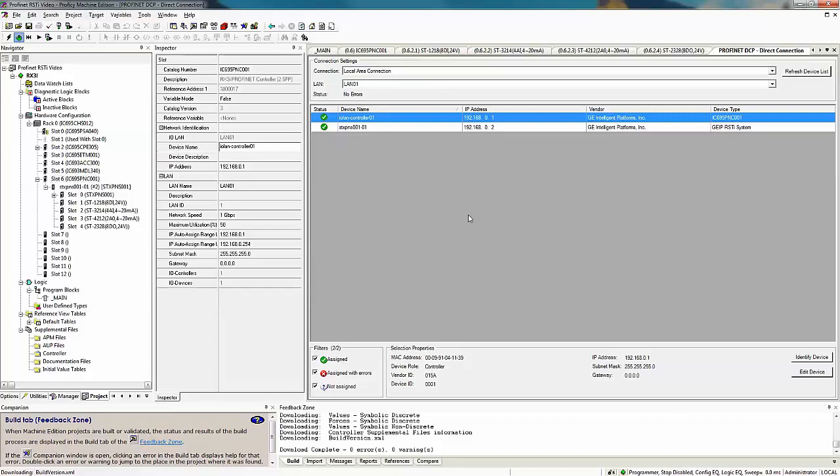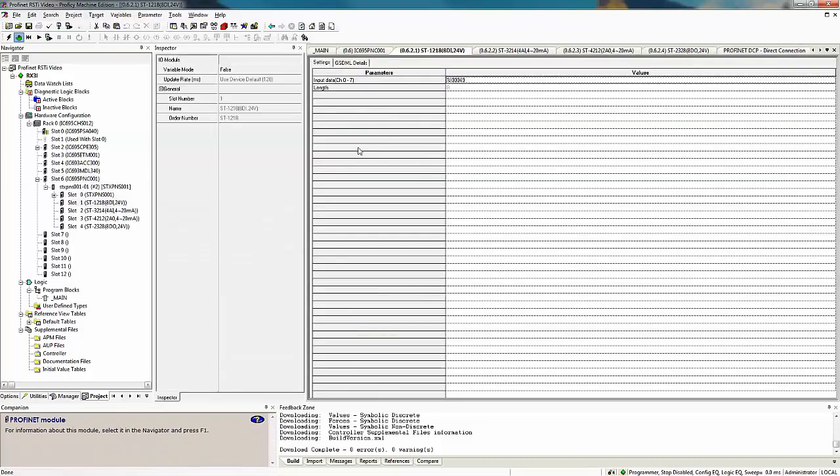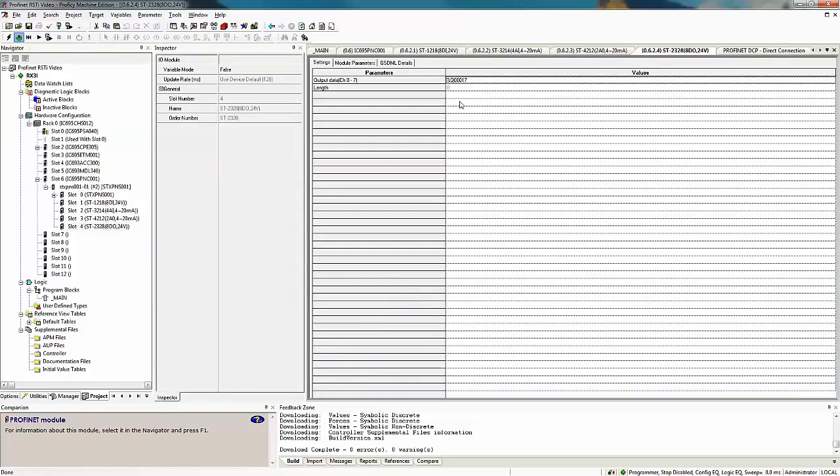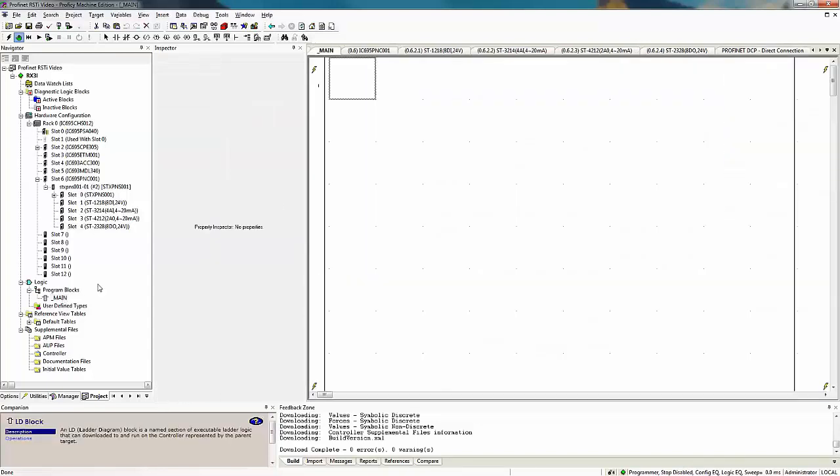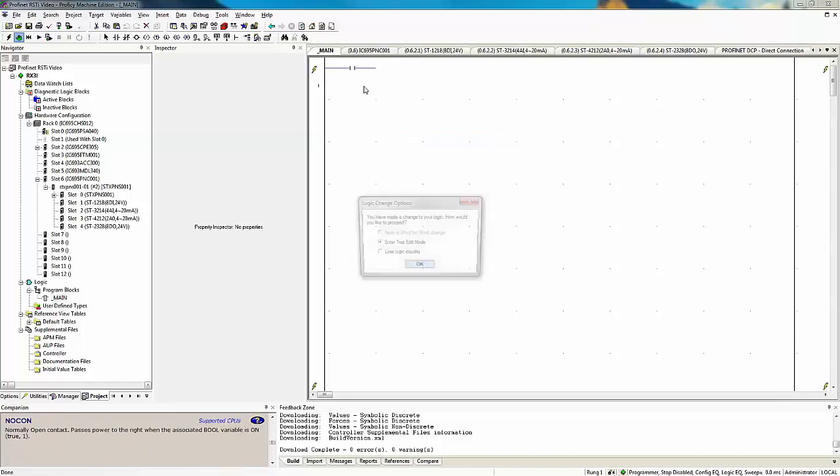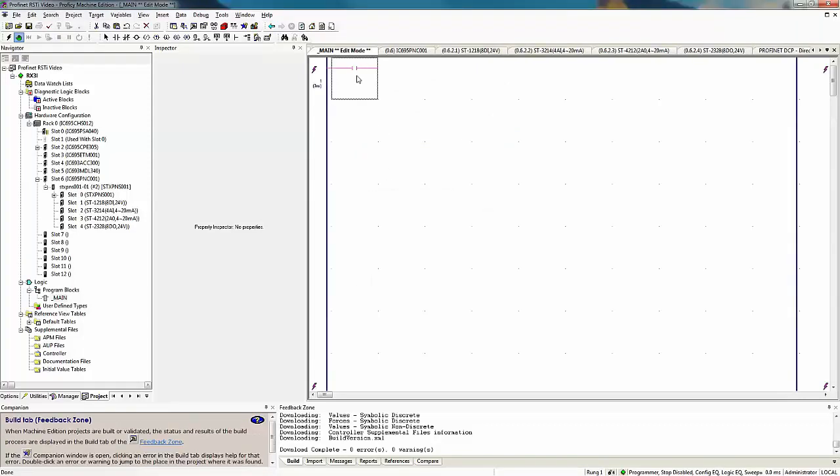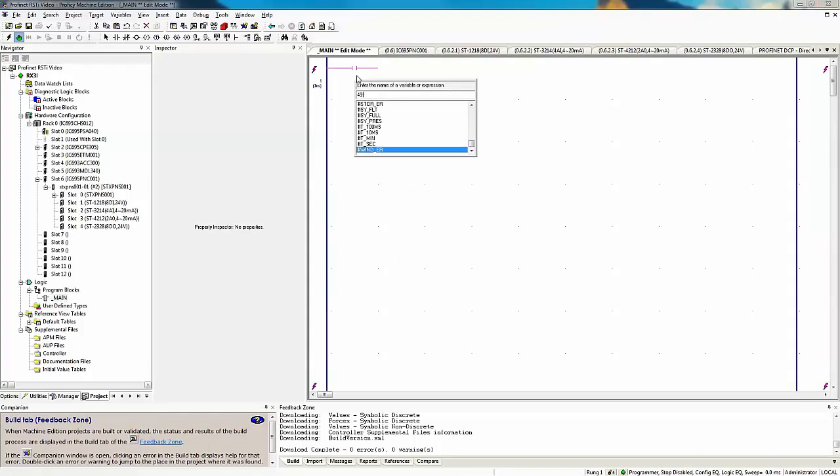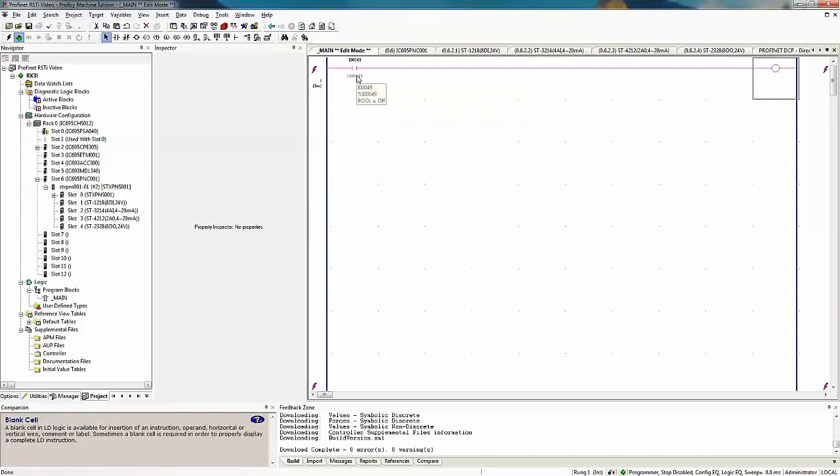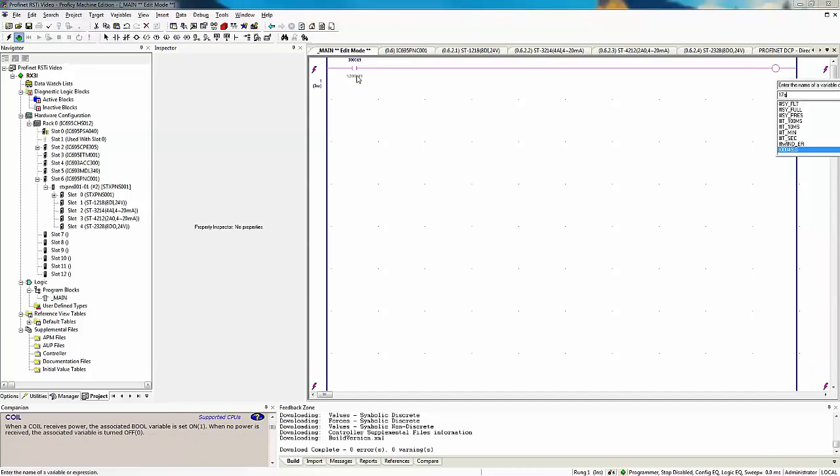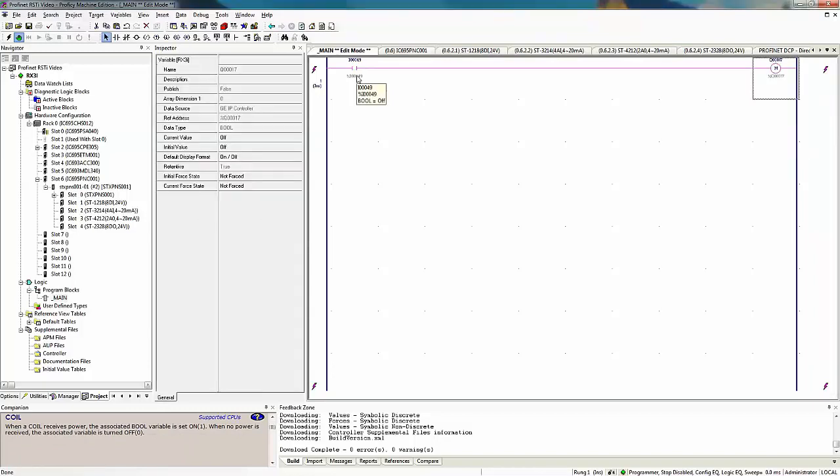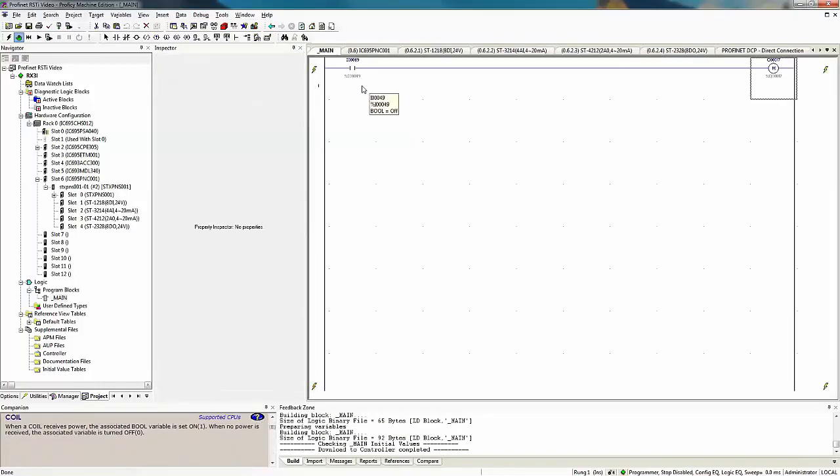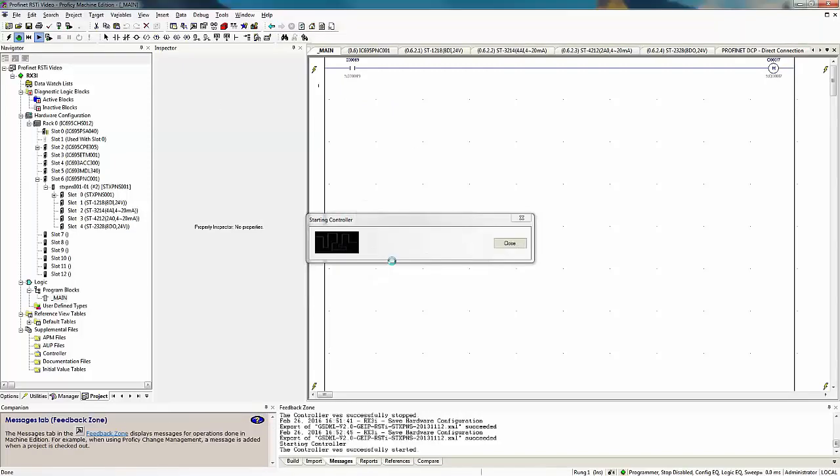Now let's say we want a simple program. If we wanted to take the very first card which is at I49 and have it turn on the very first output which is at Q17, we could simply go ahead and program that into our system by going to our main block, adding a normally open contact. We'll go into test edit mode and we'll say this one is I49 and hit enter, and we need to tie that to a coil that is going to be at Q17 for example. Then we send that down to our PLC to accept the edit. This little piece of logic will, when I turn on the push button that's tied to I49, turn on the output.